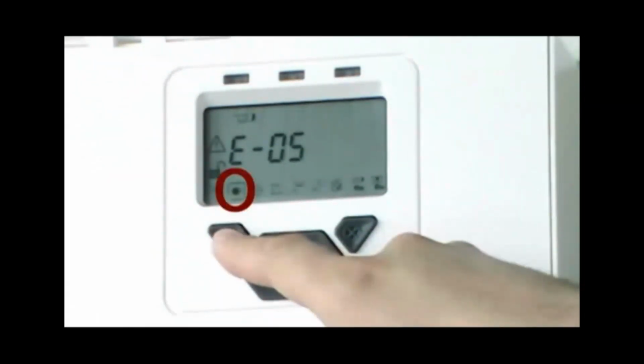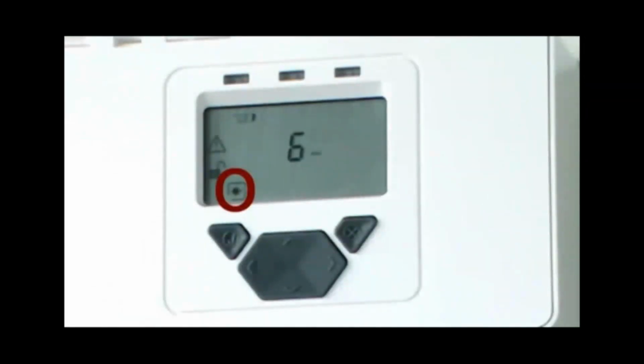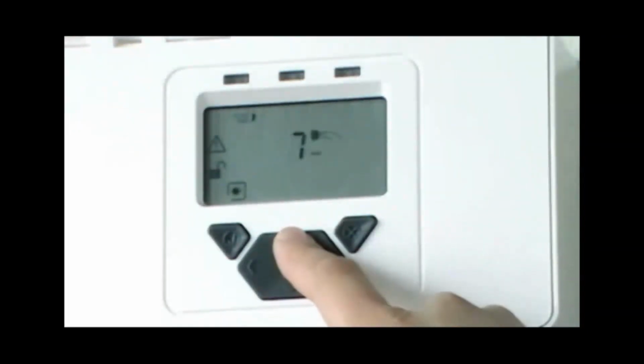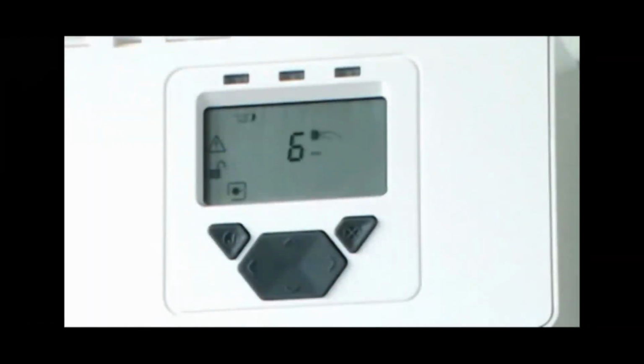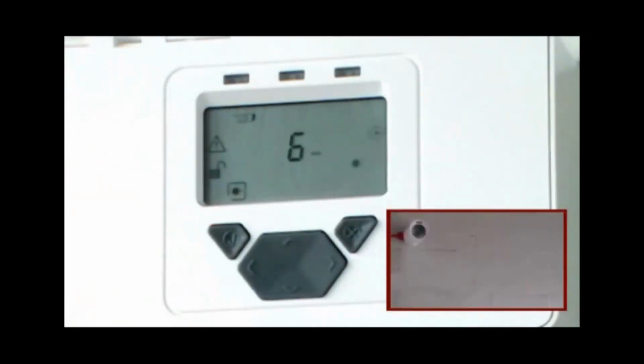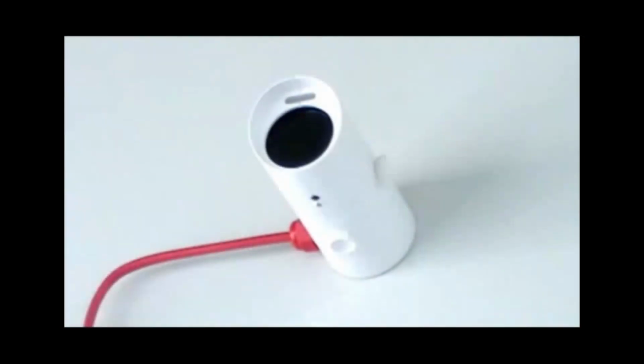The first stage of alignment is to align the receiver onto the transmitter using the integrated laser in the receiver. To activate the laser, select the second icon. The display now shows how many minutes the flashing laser will remain on for. This can be changed if required. Press tick to accept the number of minutes and turn on the laser. Whenever the laser is on, the system will be in fault. The laser can also be turned on by using the laser switch on the receiver head whilst in the Engineering menu.